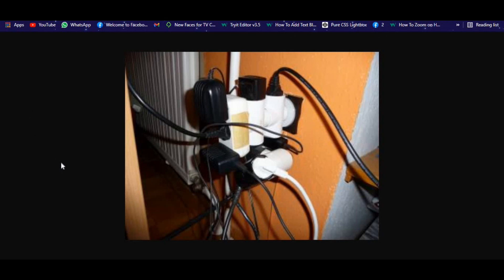As we can see in the image, lots of plugs are being plugged into one point. This is a typical scenario — we've got someone's cell phone in here, we've got a heater plugged in, which we know requires quite a bit of current. There are lots of other two-prong plugs as well. This is just a very nasty scenario, especially those plugs that have two outlets for two-prong plugs.